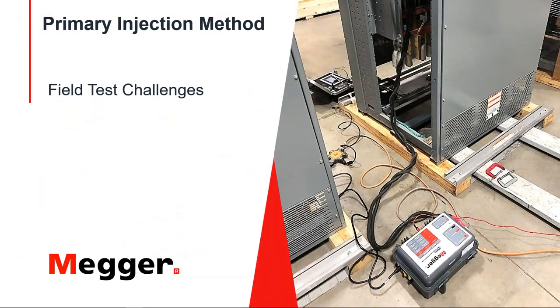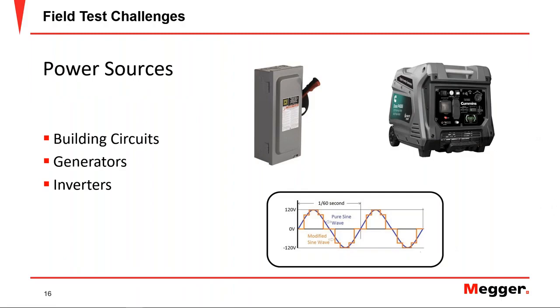Before we dive deep into the specifics of the unit, its features, its advantages, and how it makes field testing easier, let's discuss the field challenges, to better understand the features of the SPI 225. The first challenge we encounter when we need to perform these tests in the field is how we're going to power the instrument, in this case the SPI. The power can come from the building circuits if we have power in the building where we're performing the test. If not, we need to look at either a generator or an inverter.